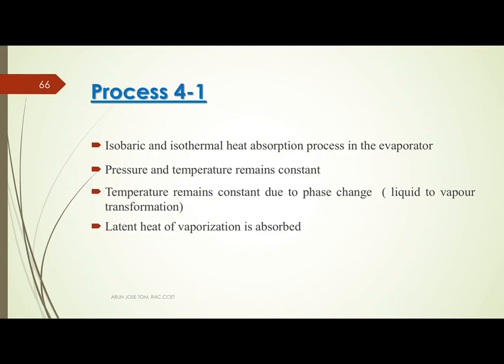The next process is process 4 to 1 — the refrigeration process in the evaporator. The process is isobaric and isothermal. The evaporator absorbs the latent heat of vaporization from the space to be cooled. Pressure and temperature remain constant due to phase change — liquid to vapor transformation. Point 4 has a lower dryness fraction than point 1, meaning vapor amount increases. The latent heat of vaporization is absorbed from the refrigerated space.